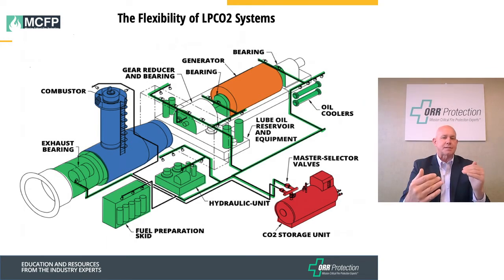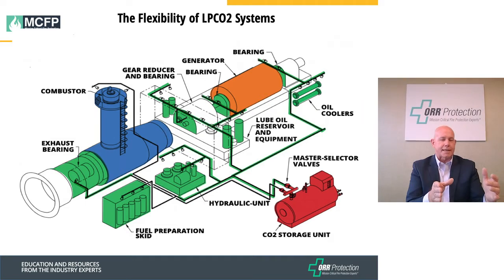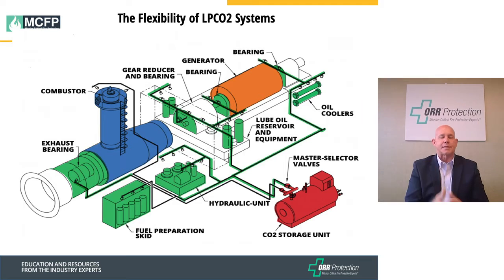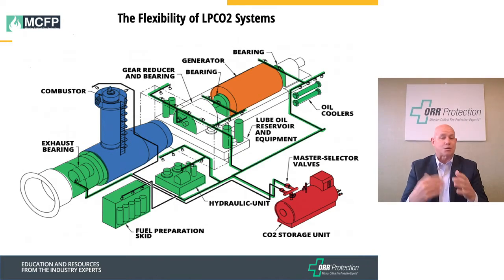A conventional or high pressure CO2 system may only be able to discharge CO2 into one zone or hazard, and after that single discharge you would have to recharge the high pressure bottles individually. The benefit of a low pressure bulk system is that we can design it to have multiple shots or multiple zones of discharge — discharging once, and again if needed, in one area.